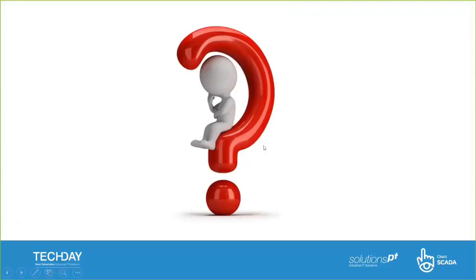That's a really good question. Thanks, Andy. Basically, the answer to that is yes. So I would, first of all, log my Citect data to my local historian on site, and then from my Wonderware historian, I would replicate that data to AVEVA Insight. That way you have the best of both worlds and all your local historizing is there. Your clients are still querying that historian for all its data. And then, of course, your remote workers or managers are able to securely look at the data from the cloud.